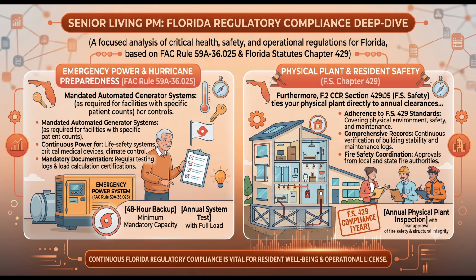Now jump across the country to Florida, where the Agency for Healthcare Administration, AHCA, enforces the Florida Administrative Code. Under FAC Rule 59A-36.025, Emergency Environmental Control for Assisted Living Facilities, Florida law dictates strict emergency generator PMs. Following extreme hurricane seasons, Florida mandates that your backup generator systems must keep resident areas at or below 81 degrees Fahrenheit for a minimum of 96 hours following a main power failure. Your PMs must log not only the generator engine, but also a 72-hour on-site fuel supply for large facilities, automatic transfer switch servicing, and carbon monoxide detector testing.